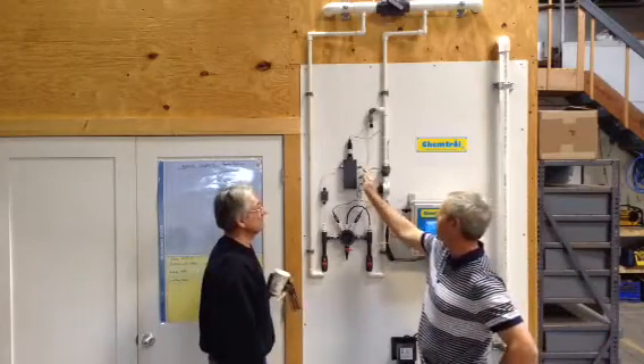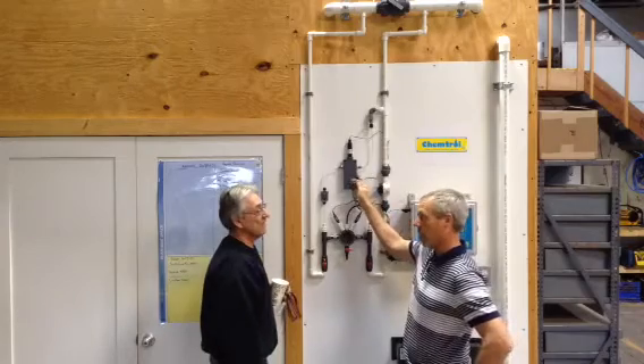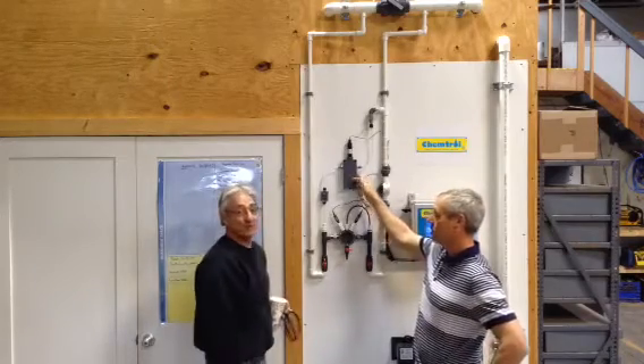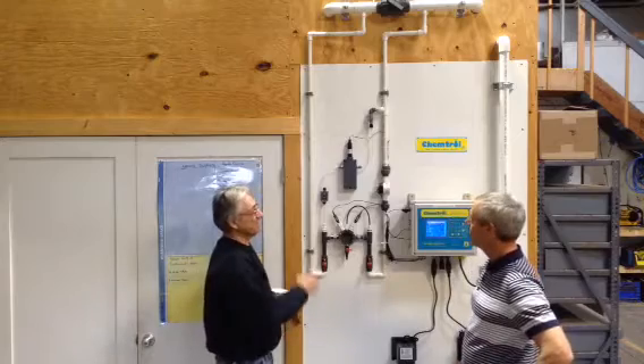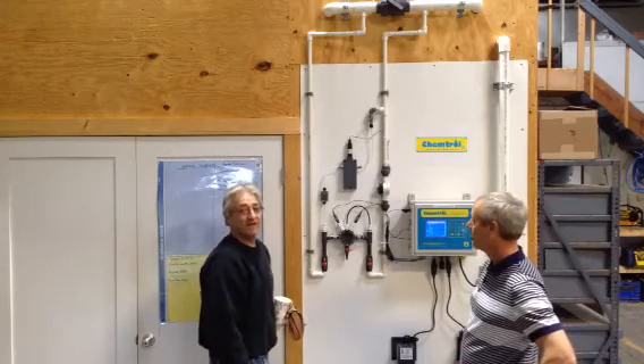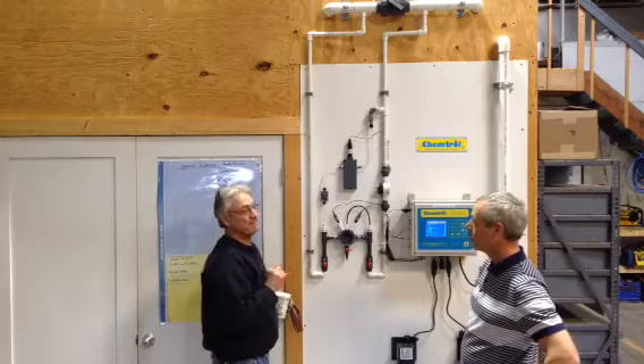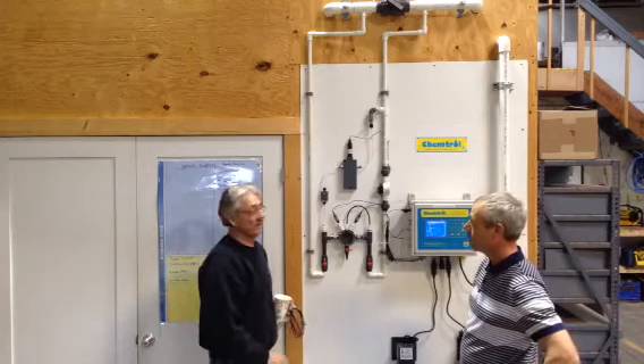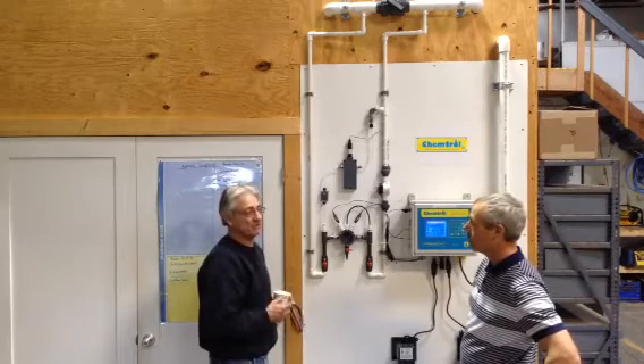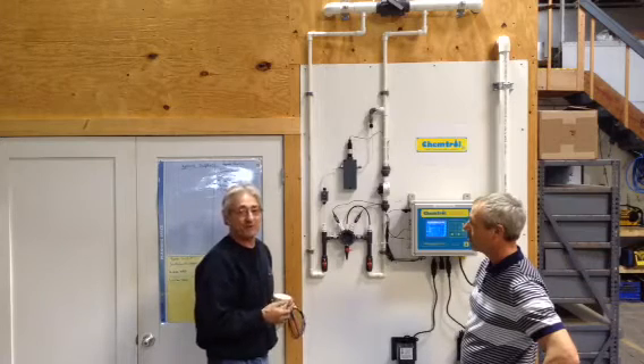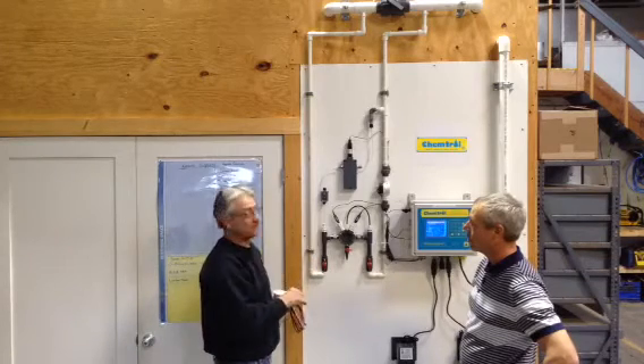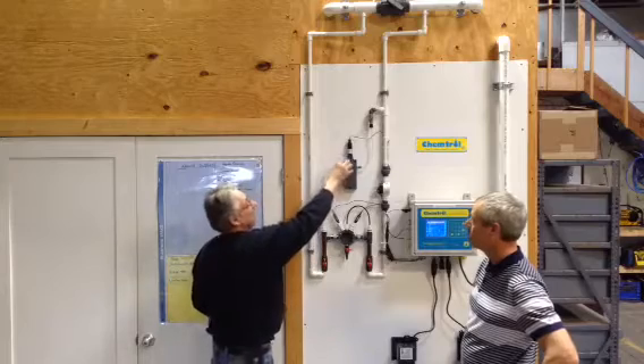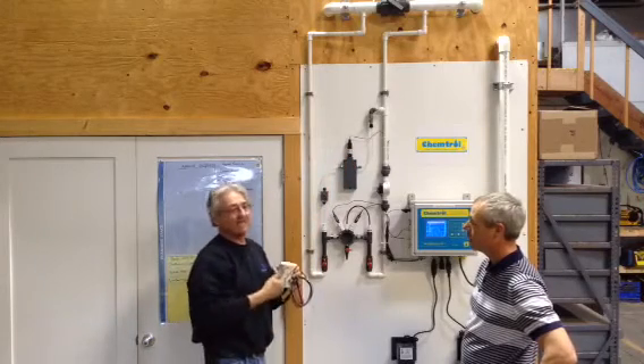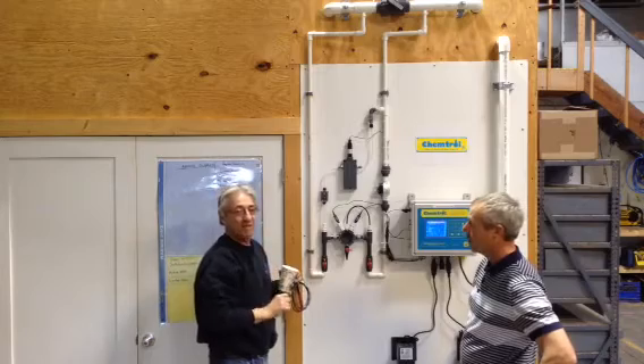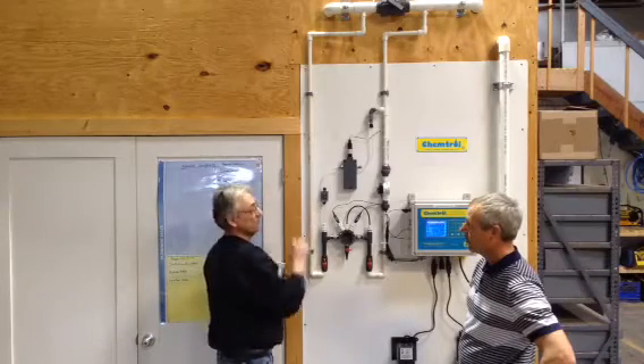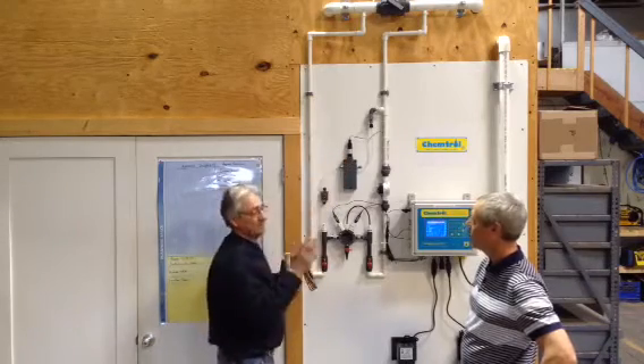Yeah, so, and this is a PPM. This is not one that you would do something like this to. No, you can't. The part per million probe is a true part per million. It actually is connected up to this Chemtrol, and it'll do part per million. There is a membrane on the end that's non-cleanable. The only thing you could possibly do is, after a year or so, if you find that it's not picking up the right reading, is you would shut off the controller, close off the sample cell, and remove the probe. Inside there, you'd pull out a membrane, put a new membrane and a new gel on it, put the new membrane on it, slide it back in, and turn it back on.